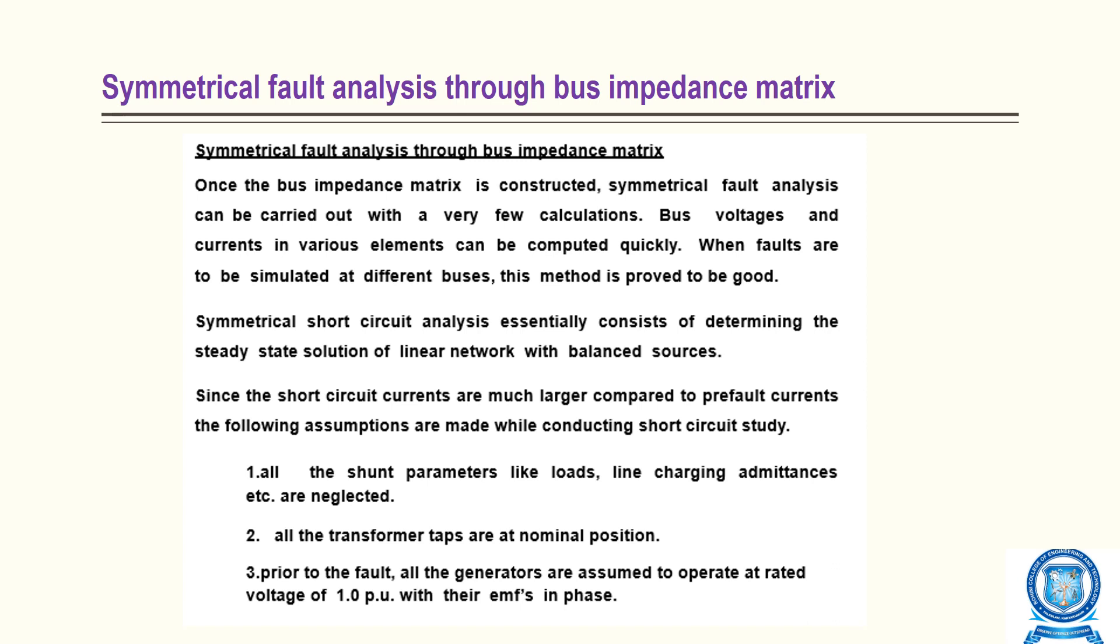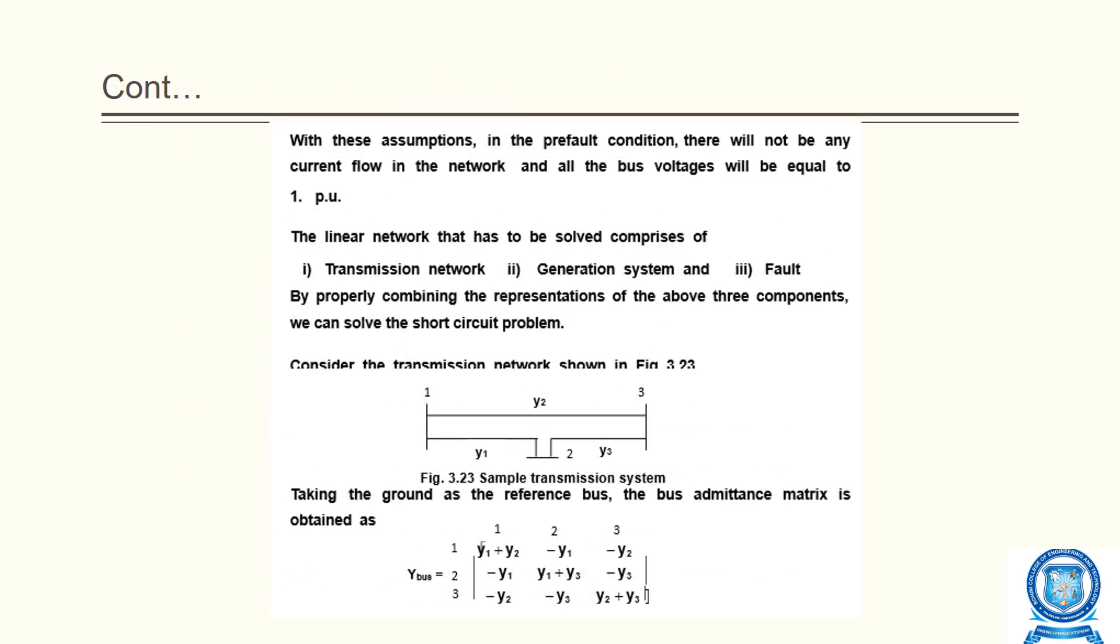Prior to fault, all generators are assumed to operate at rated voltage of 1.0 per unit with their EMFs in phase. With these assumptions in the pre-fault condition, there will be no current flow in the network and all bus voltages are equal to 1.0 per unit. The linear network to be solved comprises transmission network, generation system, and fault. By properly combining the representations of these three components, we can solve the short circuit problem.